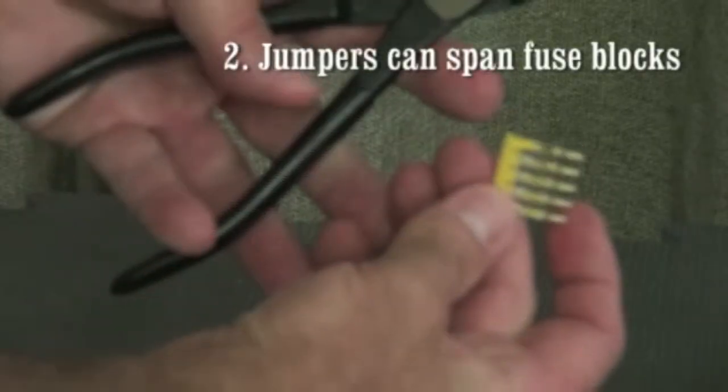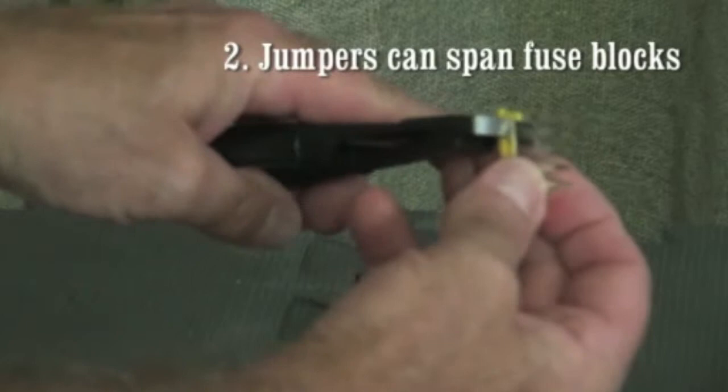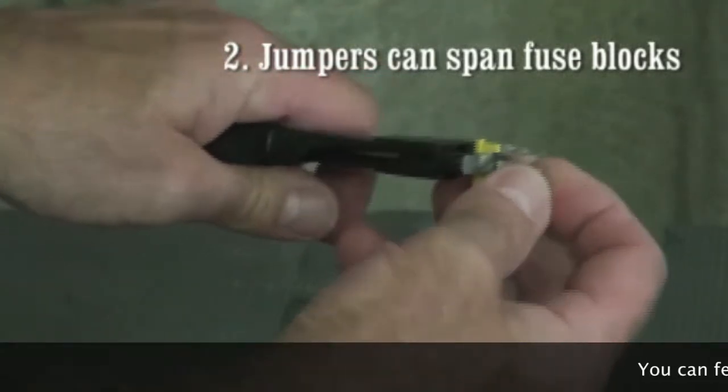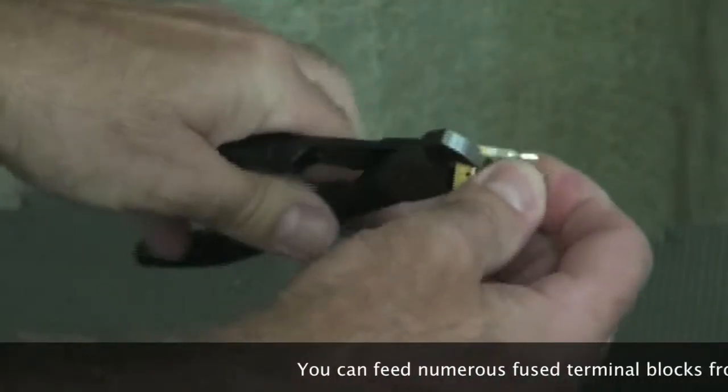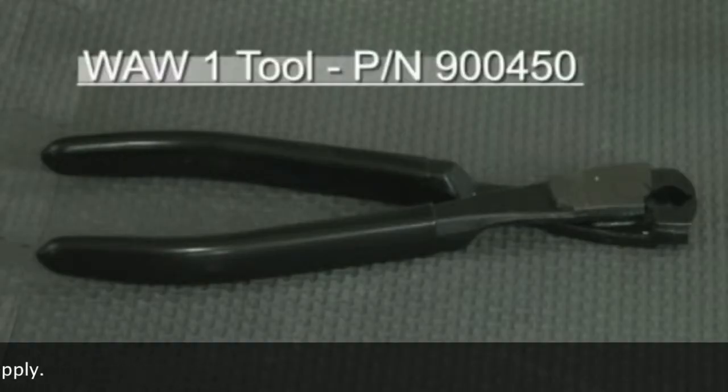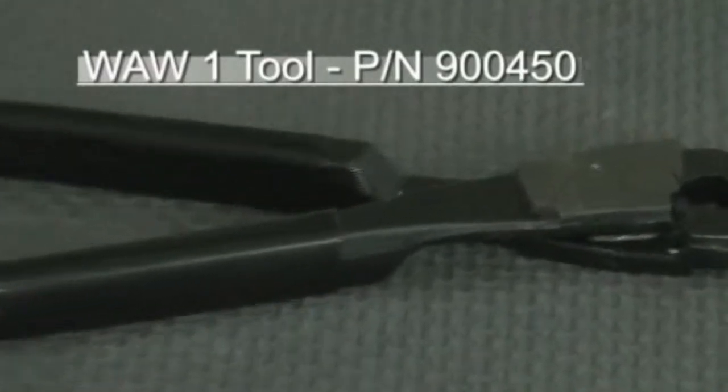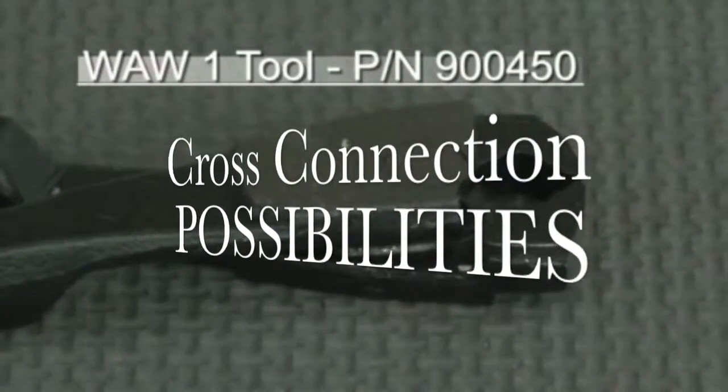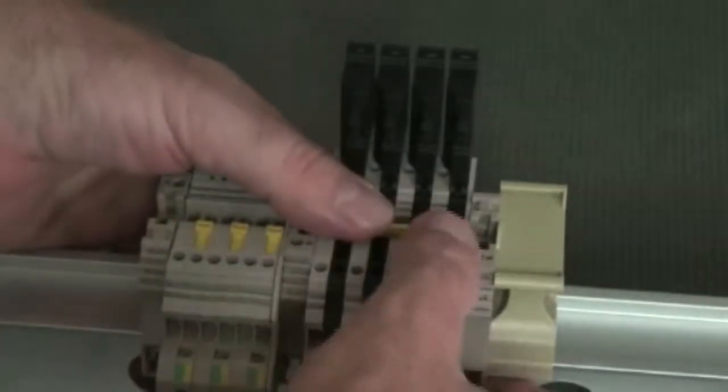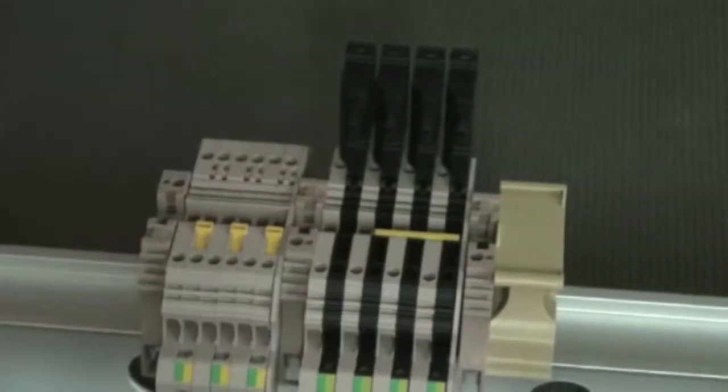Pluggable cross connections or jumpers can span across fuse terminal blocks. This means that you can feed numerous fuse terminal blocks from a single wire to your power supply. Clipping the jumpers provides you with almost unlimited cross connection possibilities. Insertion of the Weidmuller pluggable jumpers is fast and requires no special tools.